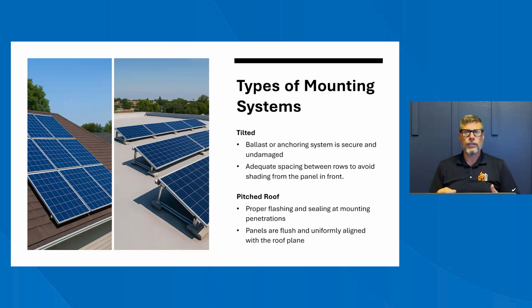What you want to look for on a tilted array when it's on the roof is whether it's ballasted properly, and is it mounted properly? Because sometimes they're just ballasted, where you have a lot of weight sitting on the anchor point, and they're not actually bolted into the roof, or they might be hard anchored into the roof. So you've got to make sure your penetrations are good, using your curb flashing up there.